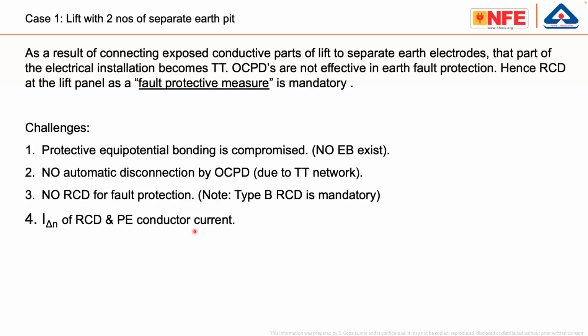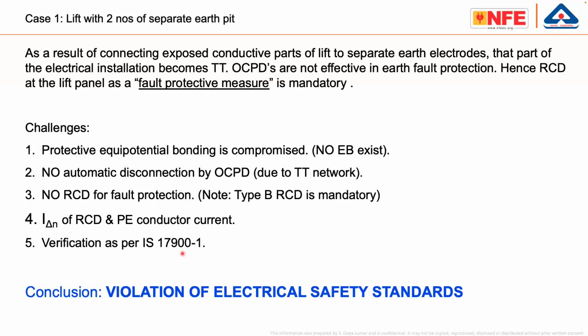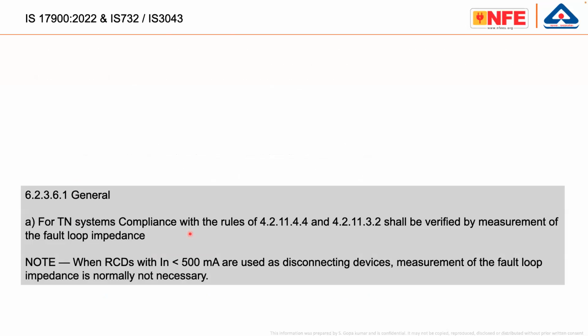Variable frequency drives always have a leakage current. Sometimes for larger lifts, the leakage currents may be much higher, maybe of the order of 500-700 milliamperes. So RCDs used with them may create nuisance tripping. Then verification. So basically, these are the violations which are happening at the moment.